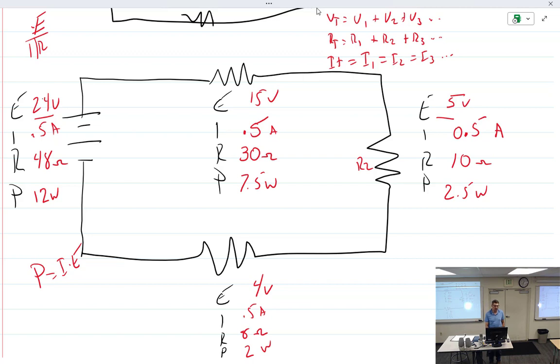Well, we've measured the voltage here. So we actually measured it. We ended up getting 24. But this right here, it's 14. This over here is like 4.5. What's going on? There could be resistance in the test leads. All right, resistance in the test leads. How would I figure out if I have resistance in the test lead?